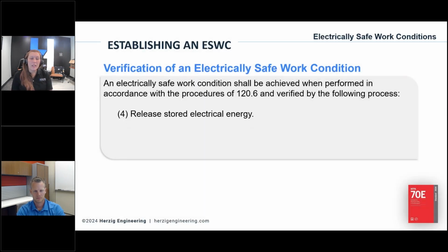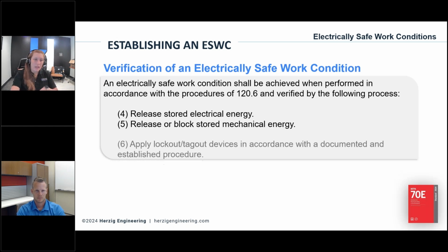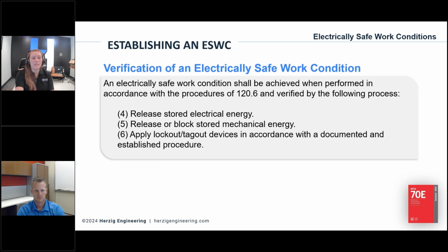Step number 4 is basically release stored electrical energy. So if you've got capacitors or something and you need to let them bleed off, let's go ahead and do that. Release or block stored mechanical energy, or really just anything that's not electrical, so that they cannot be unintentionally energized by such devices. In other words, like a motor, think about them being able to turn and start to induce a voltage. Let's not allow that to happen while you're working. And then apply lockout tagout devices in accordance with your documented and established procedure.